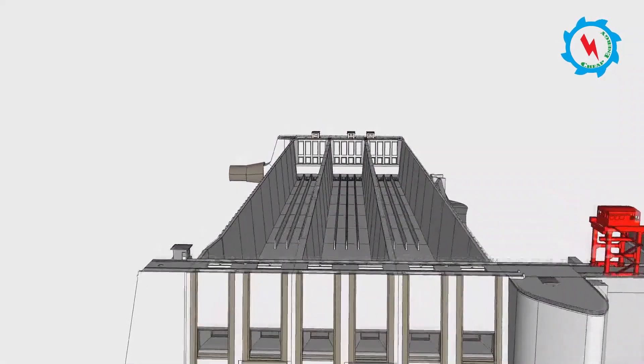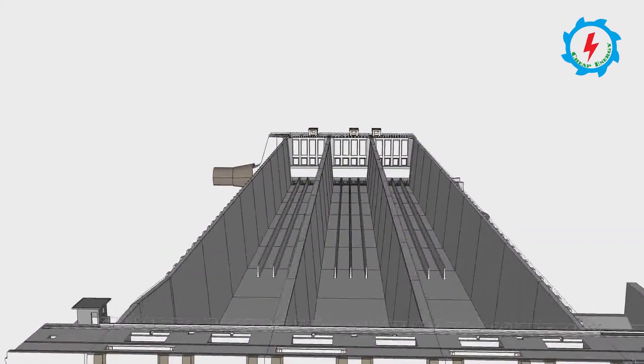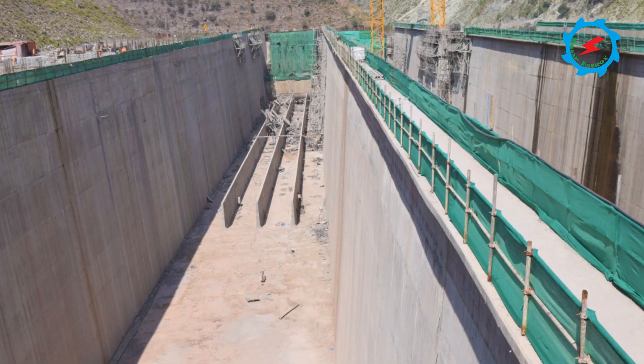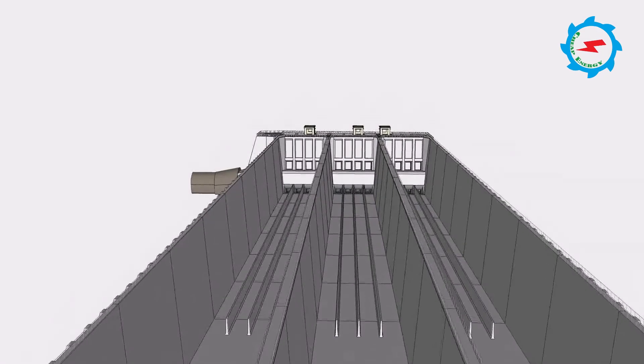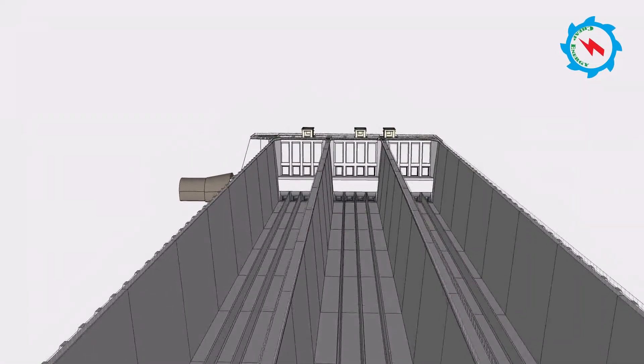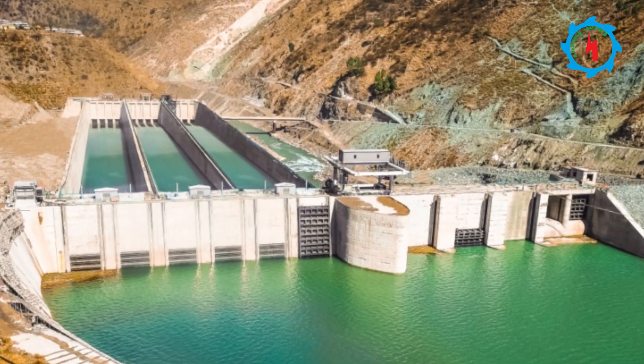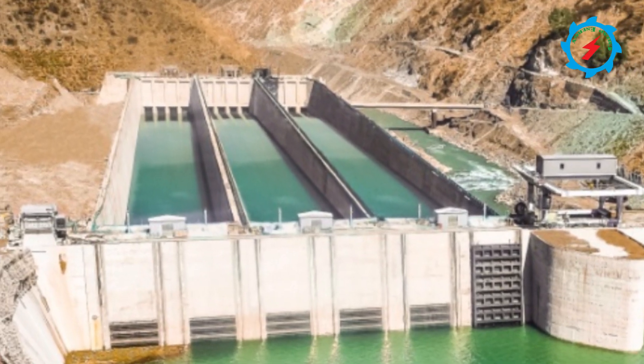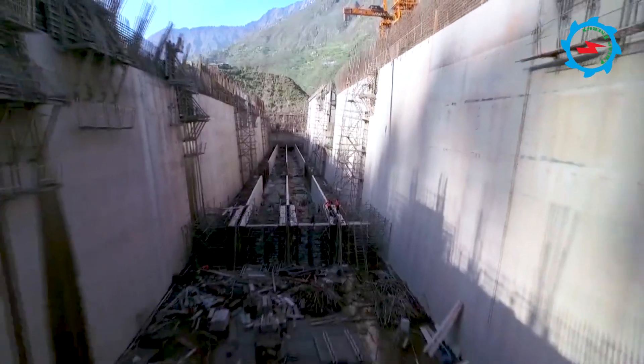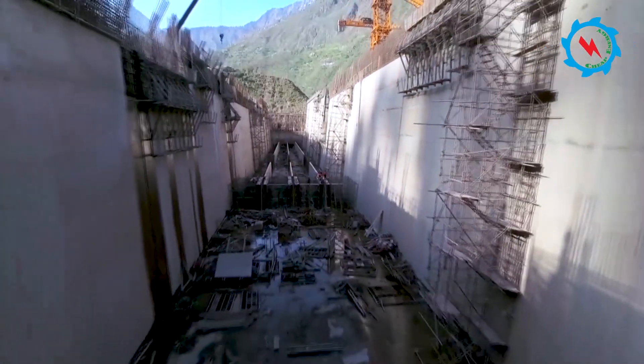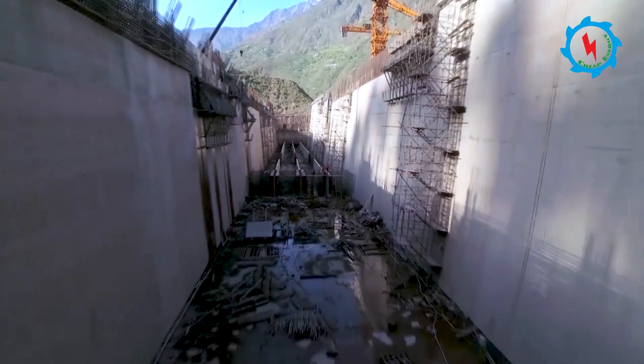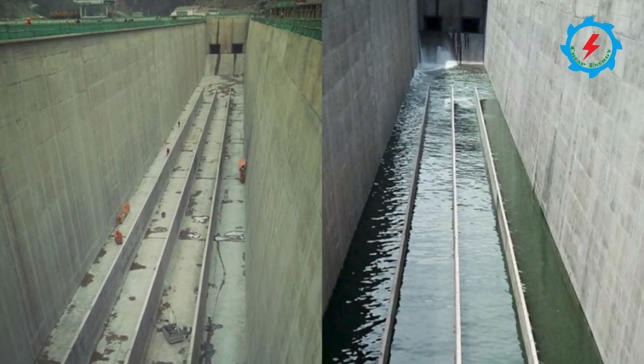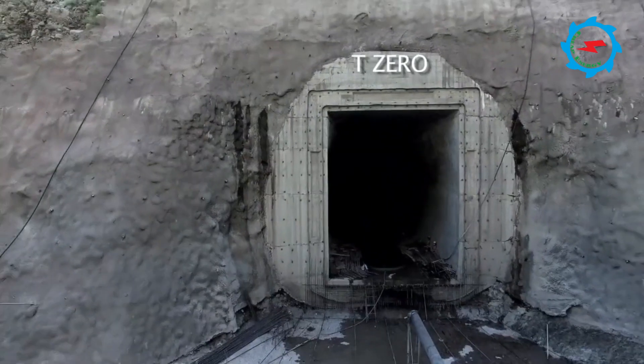Three identical bays of 275-meter long and 25.4-meter wide for sedimentation control has been arranged on the left bank of Neelum River. The velocities in the approach intake as well as in the sedimentation basin are such that most sediment particles larger than 0.2 millimeters will settle down and will not pass in the headrace tunnel to the powerhouse plant.